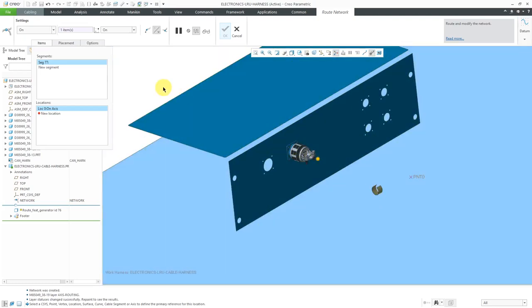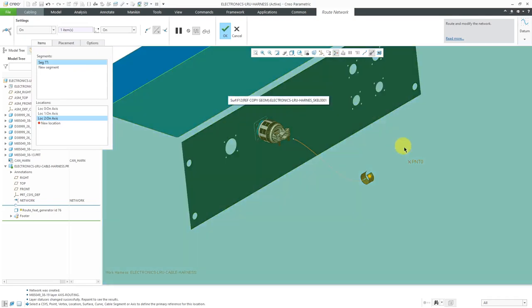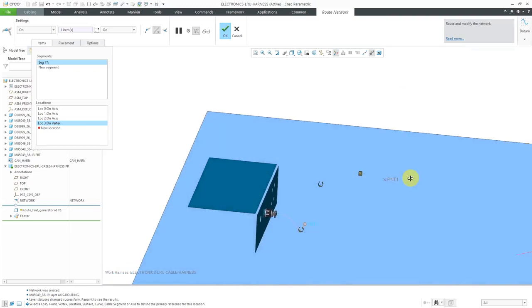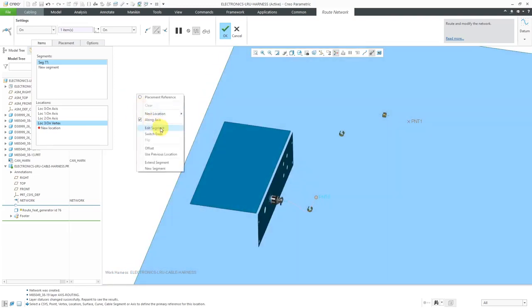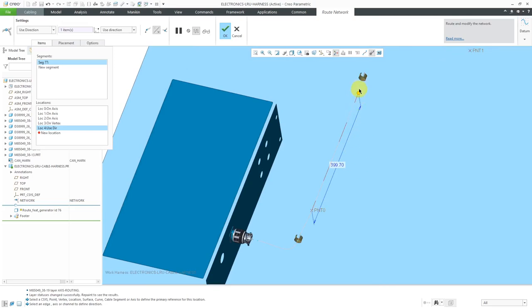Next, I want to go into the axis over here. I'll right-click and choose along axis — when you do along axis and select the axis, you get location points at each end of the axis. Then I'm going to go into this point over here. For the next location I'll choose use direction, pick this edge as a reference, and drag it out some distance. These points are on the surface — when the wire gets routed, it's going to end up being 0.6 times the diameter of the cable off of the surface, so there will be a little space between the cable and the actual surface.